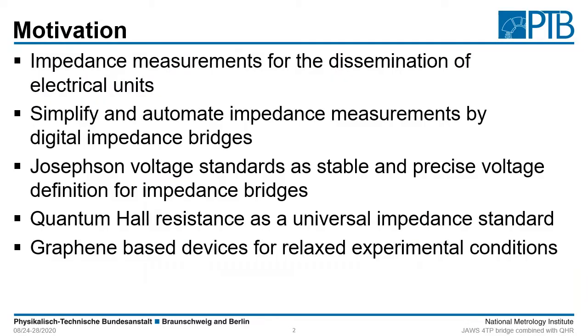The motivation of our work is to make very precise impedance measurements for the dissemination of electrical units. We want to simplify and automate these measurements by use of digital impedance bridges. When we use a Josephson voltage standard as a stable and precise voltage definition for our impedance bridge and combine this with the quantum hall resistance as a universal impedance standard, we get a very reliable and precise system.